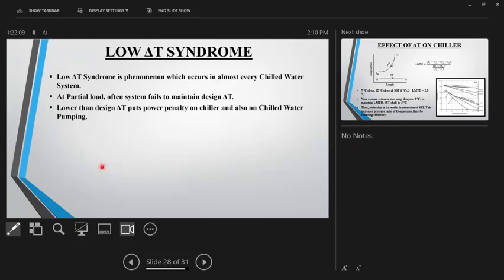I will really run fast because low delta T syndrome can itself be a two-hour lecture, so I will just try to do an introduction. Many of you might know this. Low delta T syndrome is a phenomenon which occurs in almost every chilled water system. What it means is that at partial load, often or most of the time, the system fails to maintain the design delta T. And low delta T puts a power penalty, and the chilled water pumping also increases.